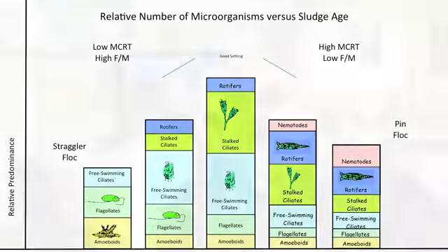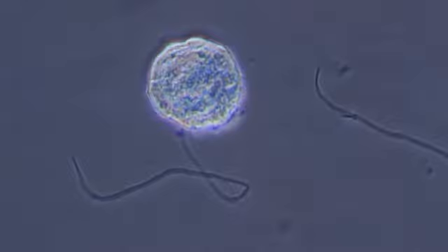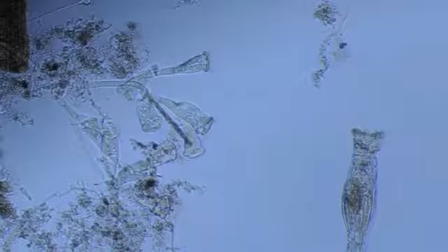As such, the tables provide a good starting point, but should only be used as a starting point, and if one wants to be certain what's going on, they develop the table for their own facility. Using these studies, one can see that when you see critters such as Vorticella, when you see the shelled amoebas, when you see some types of rotifers, you see those only when there's low BOD present in the wastewater. That's not always the case, but it's usually an indication that those conditions are present.